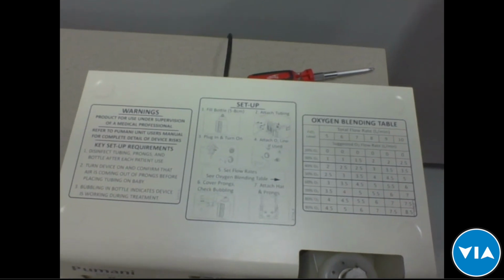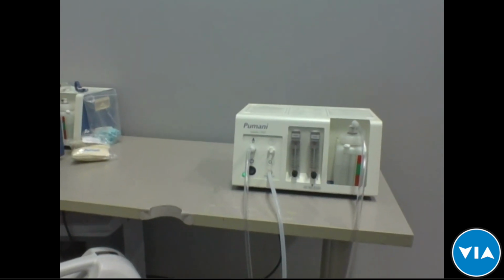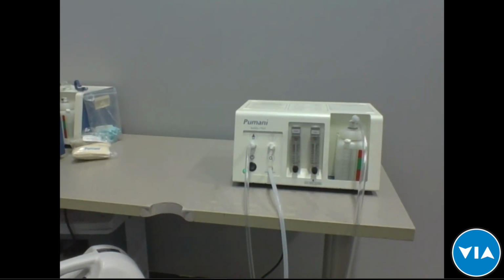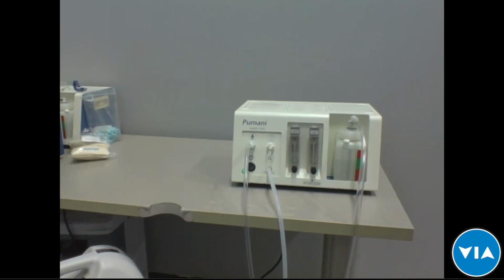And that's also one of the advantages of using the Pumani CPAP versus just the homemade CPAP. With the homemade CPAP, as you know, with the water bottle and the syringe and the tubing, you're giving the baby 100% oxygen. And that can be quite dangerous for them. And so with the Pumani, you have the ability to blend the oxygen with the air and get the amount you'd like while still providing CPAP. So there's a table, and we can go into the table later if there are more questions. I don't know if that's what you're having a challenge with, but we'll move on and we can go back. So once you've selected your FiO2, there's a table on the top, and you turn on the concentrator.